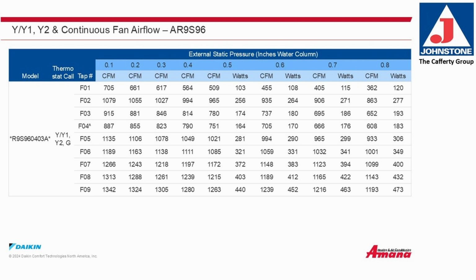Y1, Y2, and continuous fan airflow. In this chart, you'll see that I've again highlighted the external static pressure in inches of water column ranging from 0.1 to 0.8 inches. I've also highlighted the default fan speed showing its relationship to the ESP from 0.1 to 0.8 inches and how it affects the CFM and the watts of power used. Notice how as the ESP goes up, the CFM goes down, and the watts consumed goes up.